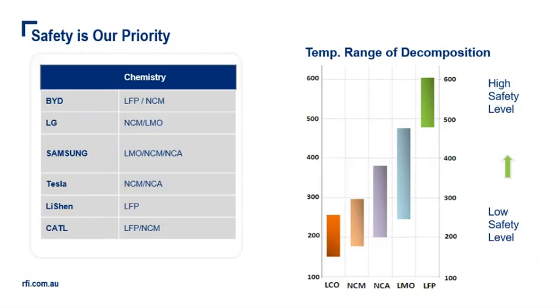The key difference between chemistries is that LFP uses phosphate for its cathode rather than cobalt, which is a very unstable element, or nickel or manganese. Lithium iron phosphate is more tolerant to full charge conditions and less stressed than other lithium-ion systems. As a chemistry, LFP provides reduced chance of thermal runaway - a chemical reaction inside a battery cell when it's unable to dissipate extra heat.